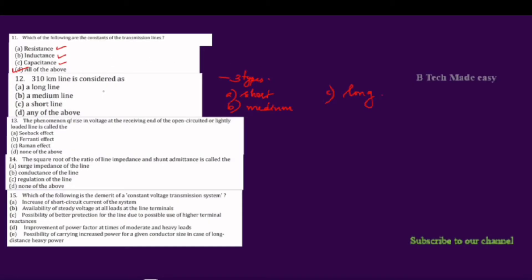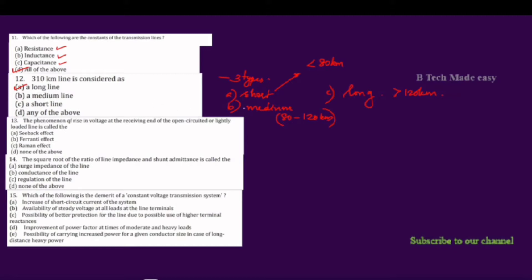If you are looking for the type of transmission line by length: up to 80 km is a short transmission line. From 80 to 120 km is a medium transmission line. Greater than 120 km is a long transmission line. So a 30 km line would be a short transmission line.